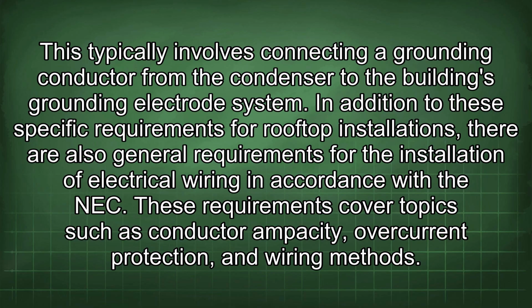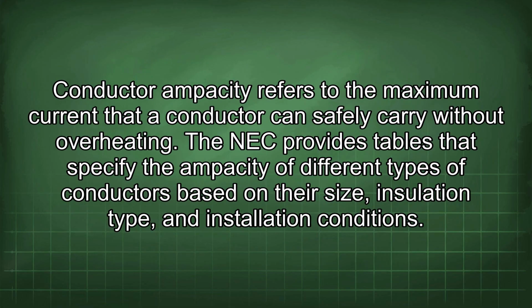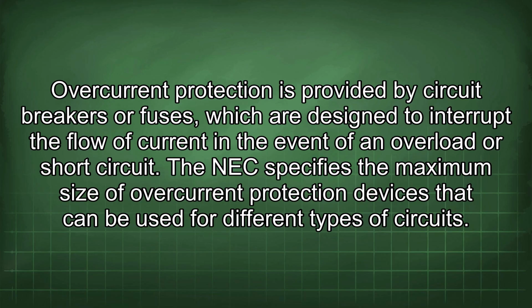In addition to these specific requirements for rooftop installations, there are also general requirements for the installation of electrical wiring in accordance with the NEC. These requirements cover topics such as conductor ampacity, overcurrent protection, and wiring methods. Conductor ampacity refers to the maximum current that a conductor can safely carry without overheating. The NEC provides tables that specify the ampacity of different types of conductors based on their size, insulation type, and installation conditions. Overcurrent protection is provided by circuit breakers or fuses, which are designed to interrupt the flow of current in the event of an overload or short circuit. The NEC specifies the maximum size of overcurrent protection devices that can be used for different types of circuits.